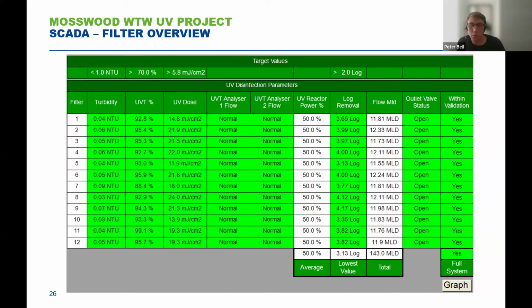Eventually we would get to a point where the power would get to 100%, and then the dose would continue to drop. After a certain while, the system would drop out of validation. So all of that data helps us understand what the performance is looking like and take preventative measures to stop that from happening. So really, really useful. But just to give a bit of context, obviously the amount of alarms from there is a huge amount of data to process. Next slide, please, Andy.